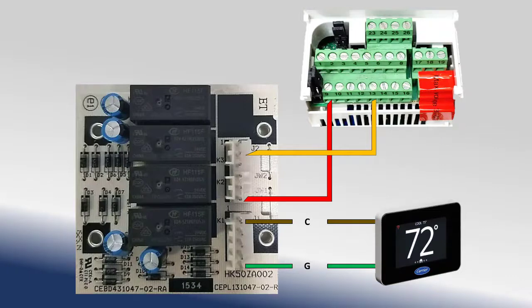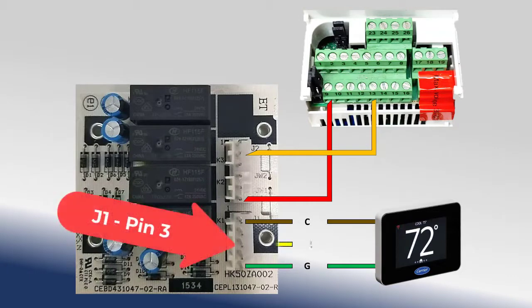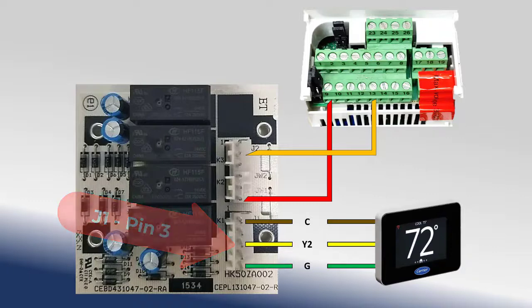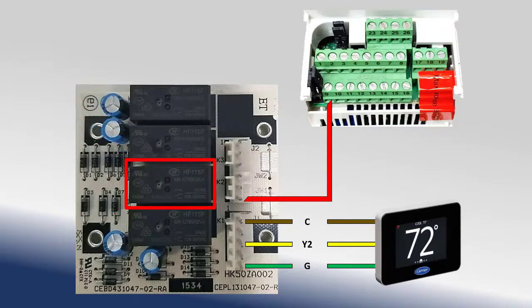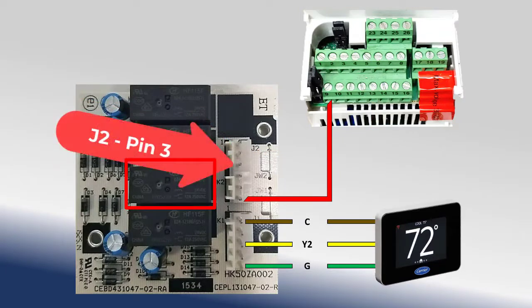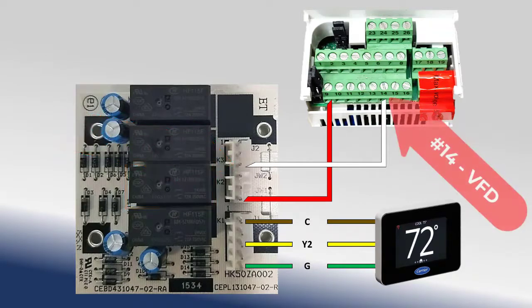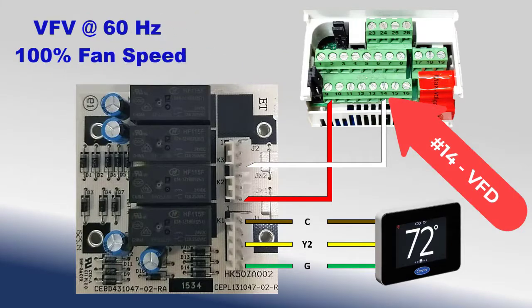During 2nd stage cooling, the Y2 signal is routed to the fan control board J1, pin 3. This closes the K2 relay. With the K2 relay closed, the 24-volt DC output at J2, pin 2 is de-energized. The output at J2, pin 3 is simultaneously energized and returned to the VFD at terminal 14, commanding the VFD to 60 Hz, or 100% of fan speed.